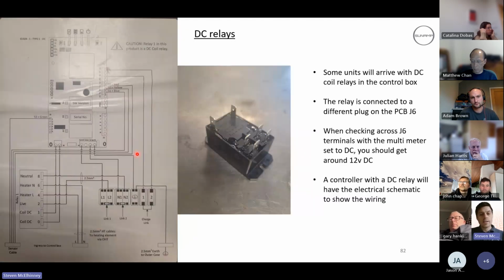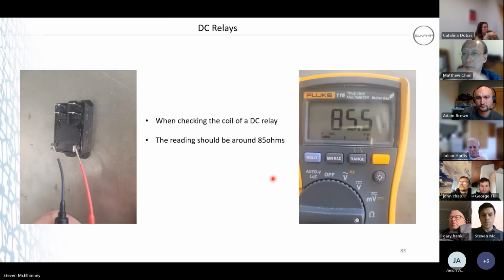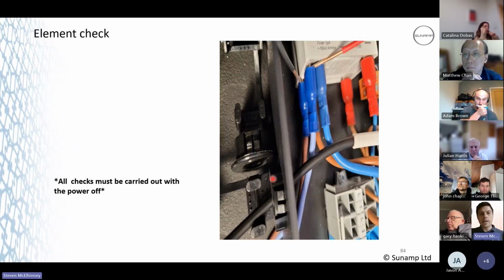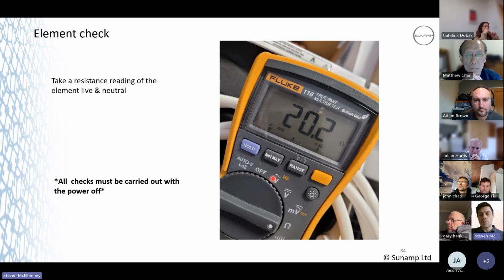So you can just get a faulty overheat stat as well. So, your AC relay, sorry, DC relay, pardon me. So again, that's your AC relay fed from these 2 points here. So that's a 240 volt AC for the white relay. The new units will be fitted with this black relay, and that's fed from here, which is a 12 volt DC. Okay. When checking across the coil of that, again, you should be getting about 85, 86 ohms across the DC coil. An element check, you should be getting between 17.5 and 21 ohms, live and neutral.